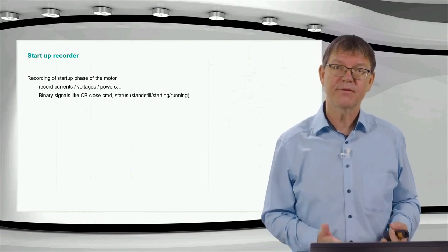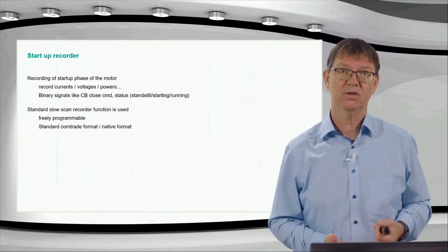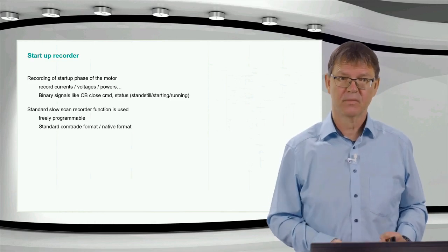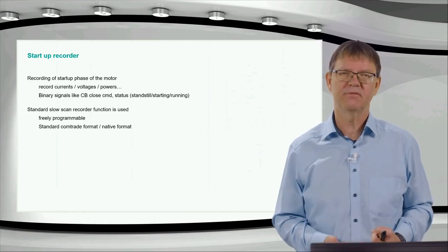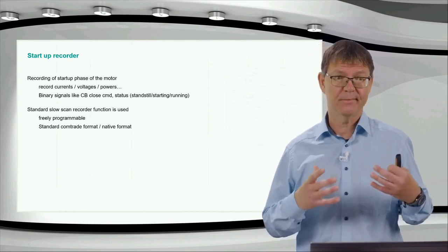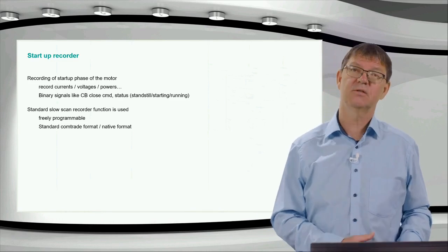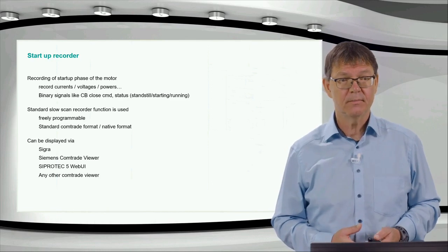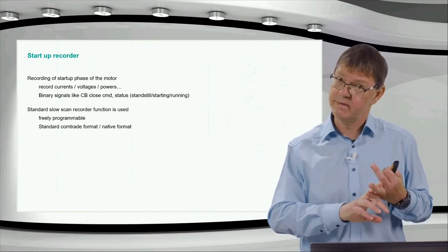This is a flexible thing because it is based on the standard slow scan recorder function, which we have now implemented in all SIPROTEC 5 relays, among other standard functions coming from the fault recorder device 7KE8. So all the SIPROTEC 5 relays have this slow scan recorder function, and we profit from it because we use it for the motor start log. It's freely programmable and it's a standard COMTRADE format or also a native format.